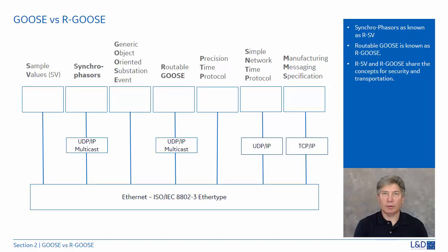Here we have a list of protocols that are available with a sample value, SV. Synchrophasors are now known as the routable sample values, RSV. The GOOSE message. The routable GOOSE, or the R-GOOSE. PTP, Precision Time Protocol, and also IEEE 1588. SNTP, Simple Network Time Protocol, and MMS, Manufacturing Messaging Specification. You'll see the only difference between the GOOSE and the R-GOOSE is the UDP IP header. The guidelines for synchrophasers as far as security and transportation have been adapted to the routable GOOSE. In the next section, we'll take a look at how we secure the R-GOOSE.